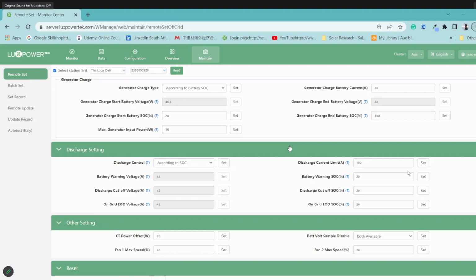What I've seen is, most lithium batteries recommend an end of discharge around 47 to 48 volts. If you set the system at 48, and suddenly you get a big load, the system kicks out the battery because you go below that 48. But when that load switches off, you find your battery is now at 49 volts. How does one get around that? Because it's not a true reflection of the battery voltage.